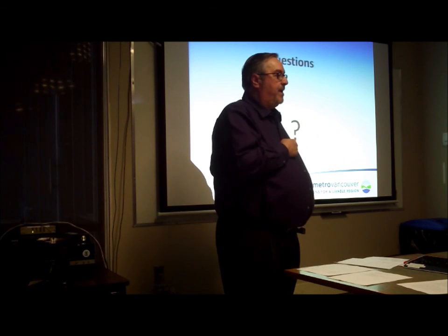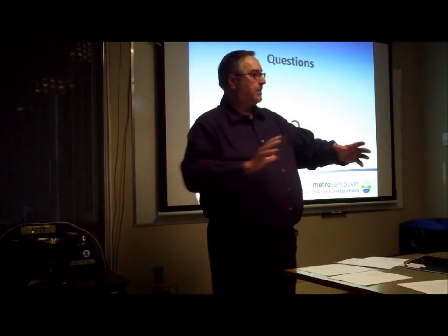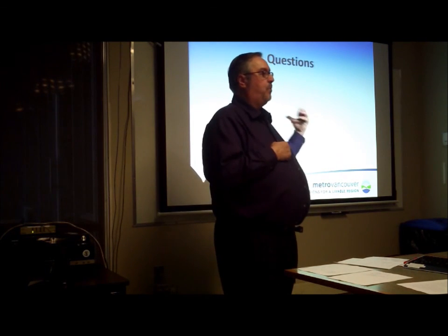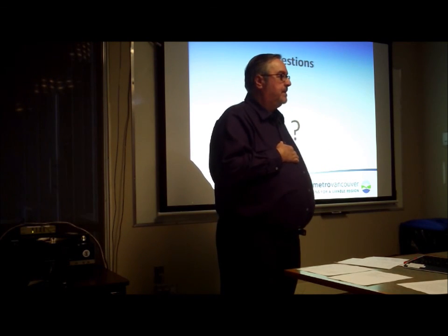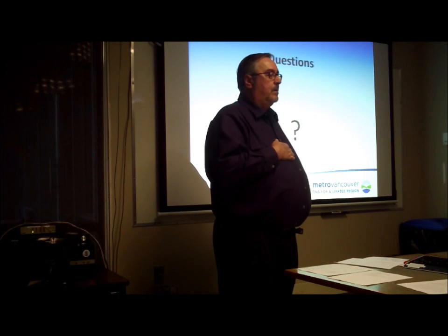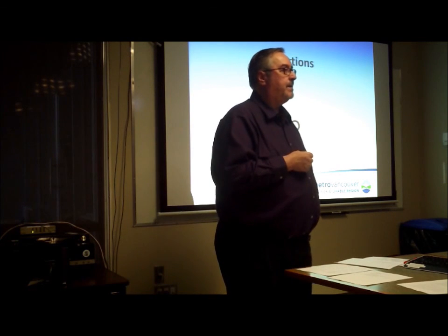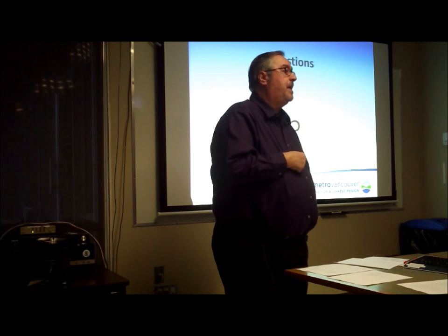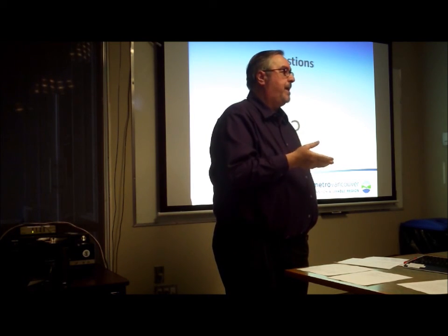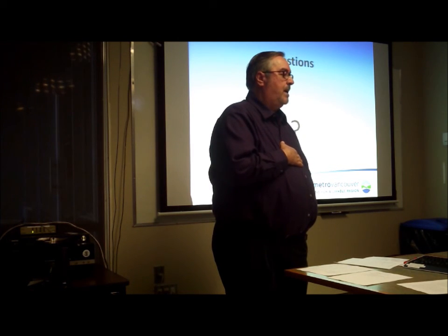The storm flows that we have at Iona would be terrible. If we can't control that somehow or bypass it some way, that could wash out clarifiers, which you could lose a significant amount of your biomass. City of Edmonton has a treatment plant slightly smaller than the Annacis plant. They have a lot of combined sewers in the downtown area. So when they get a significant rainfall, it can overload their secondary treatment capacity.